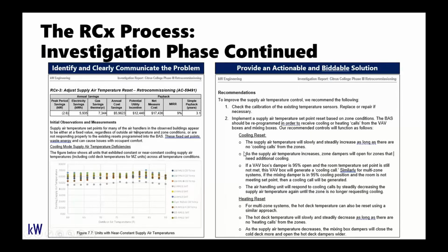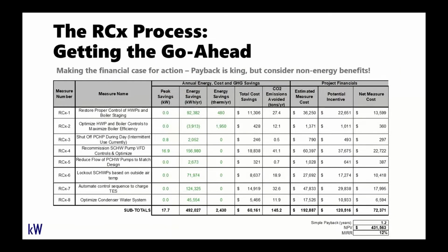So this is just a snippet of a report. The overall report will typically begin with what ends up being, in most cases, one of the most important things, which is the overall financials of the project. Here is a sample summary from the first project we did with Fred, which was the central plant retro-commissioning. We have a number of different RCX measures listed here, from some pump control, some boiler efficiency upgrades, some adjustment to the thermal energy storage sequences. We have our calculated energy savings, cost savings, and then the estimated measure cost. This is always a tough one to dial in, and this is where having that really detailed scope and recommendation is going to help dial those costs in as closely as possible.